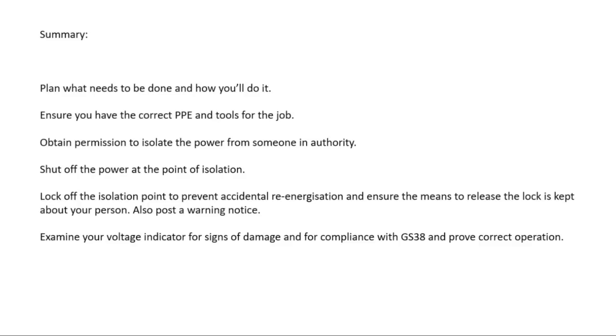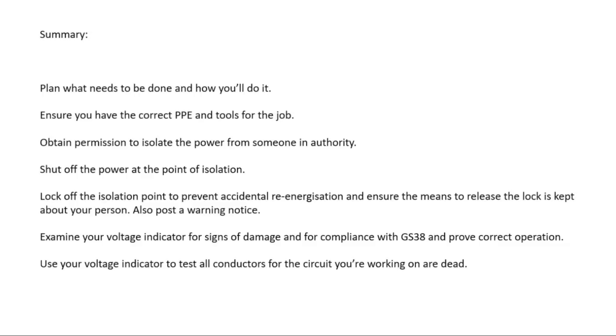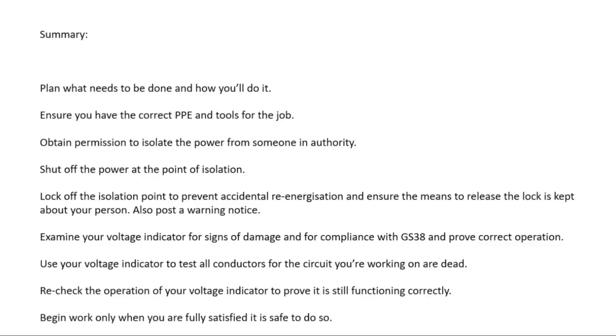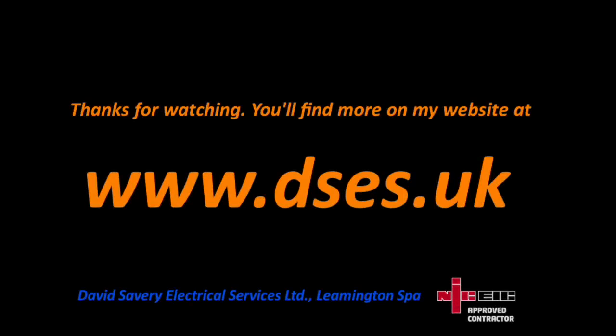Examine your voltage indicator for signs of damage and for compliance with GS38 and prove correct operation. Use your voltage indicator to test all conductors for the circuit you're working on are dead. Recheck the operation of your voltage indicator to prove it is still functioning correctly. And begin work only when you are fully satisfied it is safe to do so. Remember, it's kill the power or kill yourself in this game.